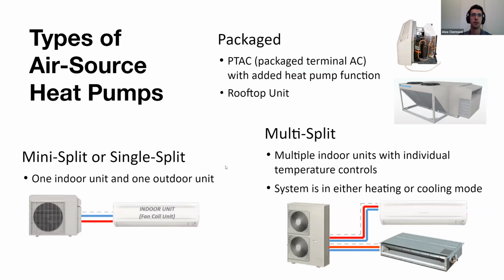Now I'm going to start with the different types of air source heat pumps. Top here in the right corner, you can see a PTAC and a rooftop unit. PTAC is often seen in hotels or apartments. It takes heat from the room and throws it outside. Some of them come with heat pump function as well. Again, that key component being the reversing valve, as we previously talked about. And then it's going to throw heat from outdoors to indoors. These don't actually work down to very low temperatures, so oftentimes you see these with electric heat in there as well. Now rooftop units can also come as heat pumps.